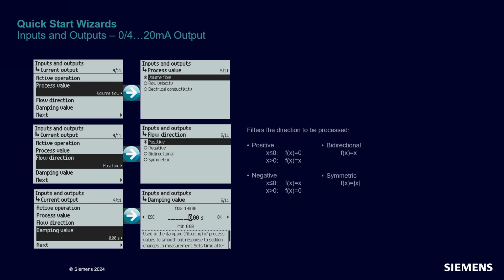You can also impose a constraint on the output based on your application. For example, you may elect to have zero output when the flow is calculated as negative — you can pick one of four modes. You can also apply a damping filter at the output by setting the time constant. This is a simple first-order low-pass filter, which means the time constant represents the time it takes for the output to reach 63% of a step change.